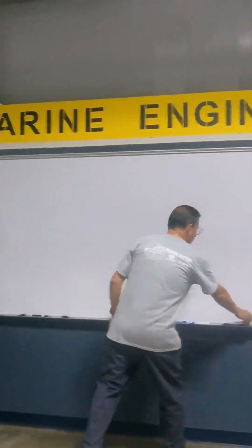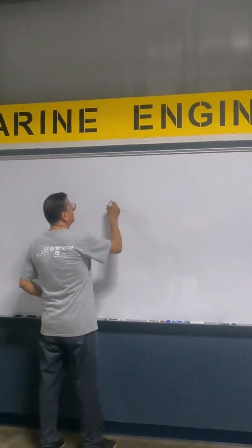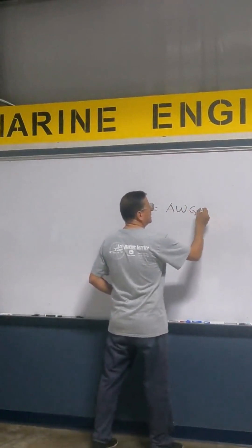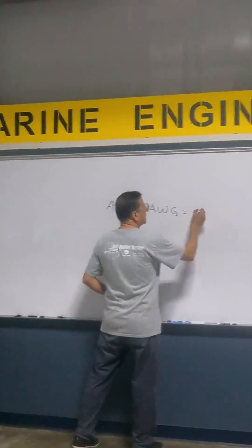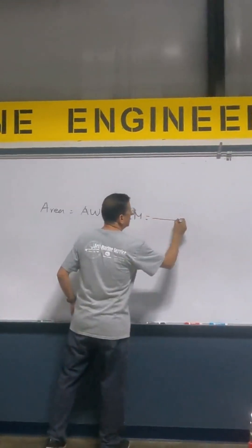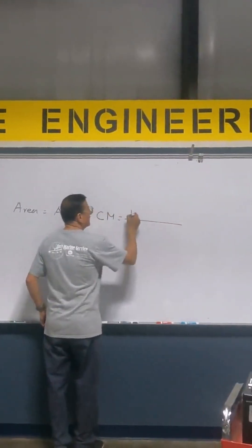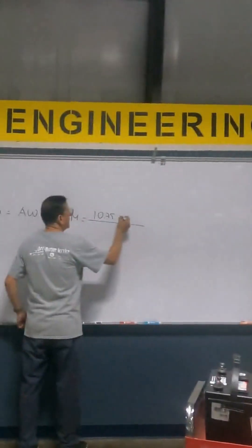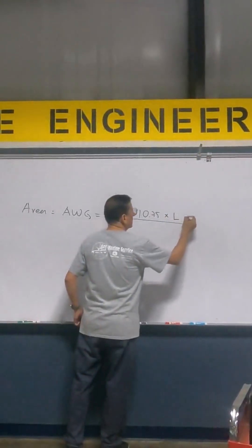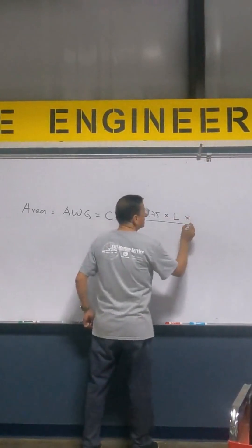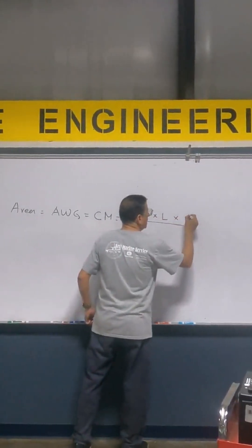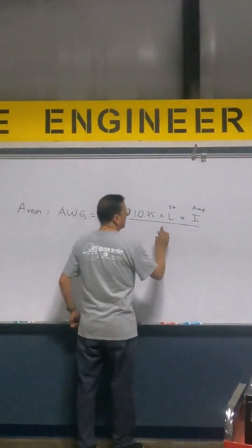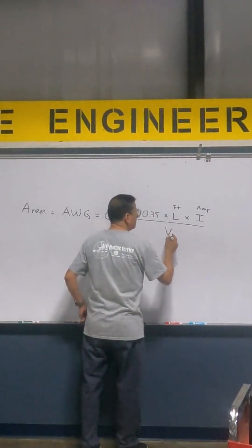What is the meaning of circular mils? The area, AWG, is in circular mils and is calculated as: 10.75 times the total length of the cable, times the intensity in amps, divided by the voltage drop.